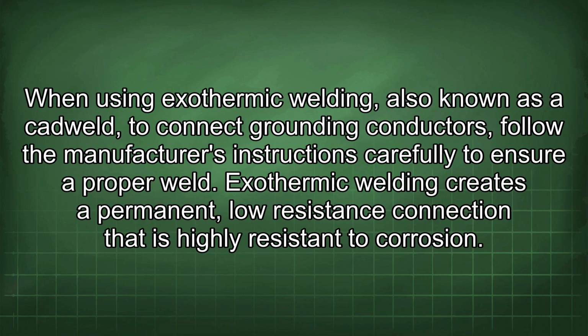When using exothermic welding, also known as a Cadweld, to connect grounding conductors, follow the manufacturer's instructions carefully to ensure a proper weld. Exothermic welding creates a permanent low-resistance connection that is highly resistant to corrosion.